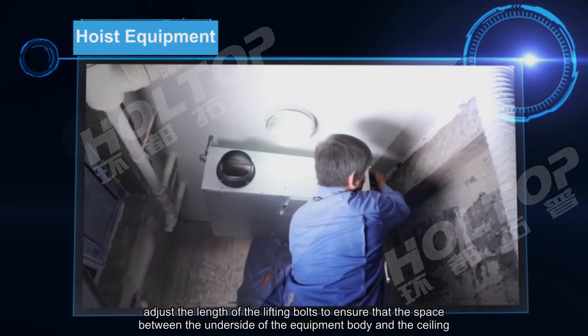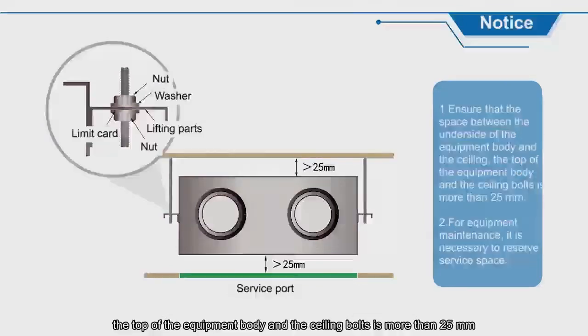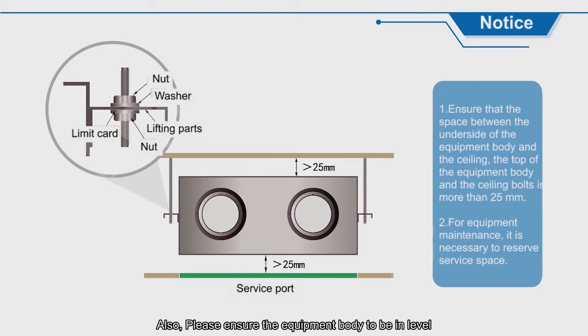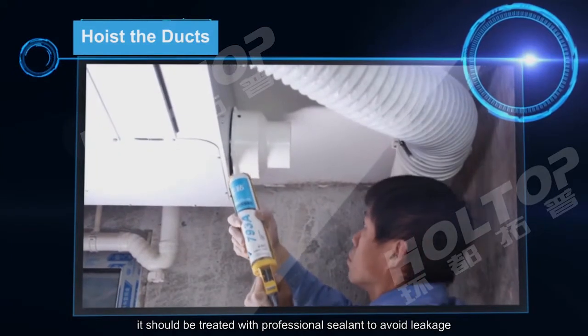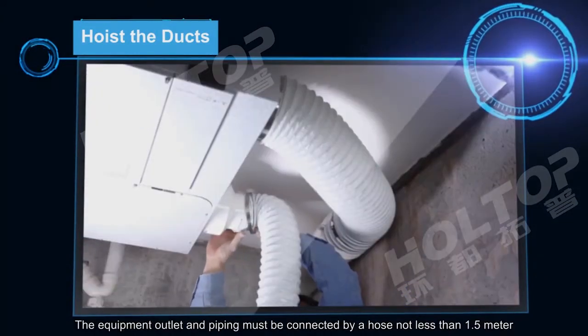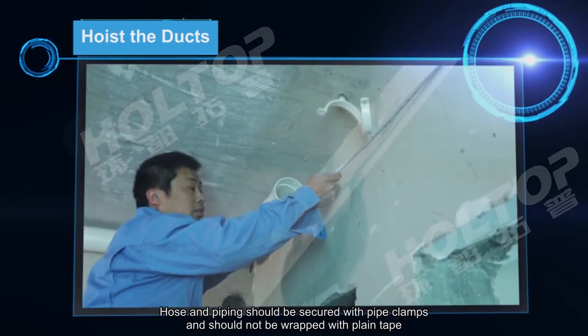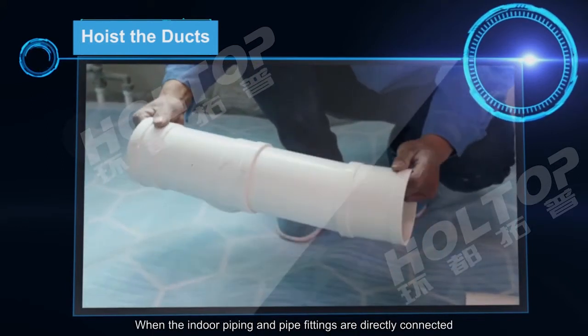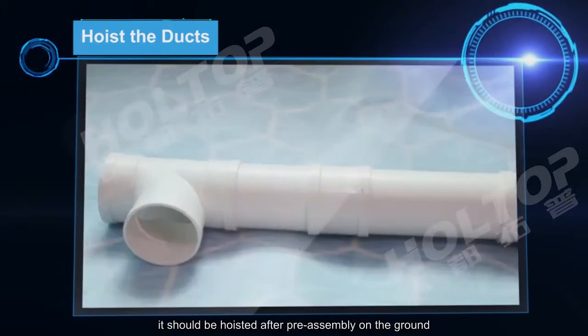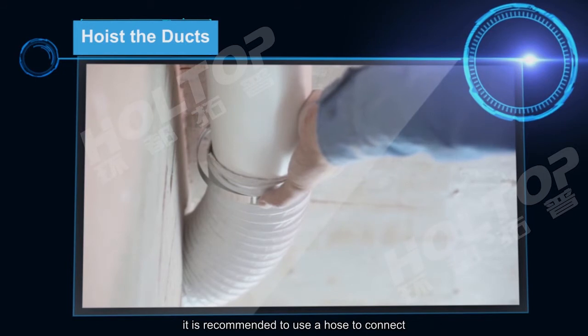After the equipment is hoisted, adjust the length of the lifting bolts to ensure that the space between the underside of the equipment body and the ceiling, and between the top of the equipment body and the ceiling bolts, is more than 25mm. Also, ensure the equipment body is level. When the air outlet of the equipment is directly connected to pipe fittings, it should be treated with professional sealant to avoid leakage. The equipment outlet and piping must be connected by a hose not less than 1.5m. Hoses and piping should be secured with pipe clamps and should not be wrapped with plain tape.